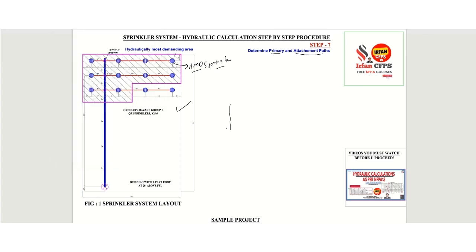This is the riser. For example, here we are having plans. This is the riser, we have one gate valve here and one check valve. Now this is going to the sprinklers. We are going to draw only those sprinklers shown in the hydraulically most demanding area. Since this cross main is rising, we have raised till three feet and we are drawing the branch lines and showing the upright sprinklers, since in this project we have considered upright sprinklers.